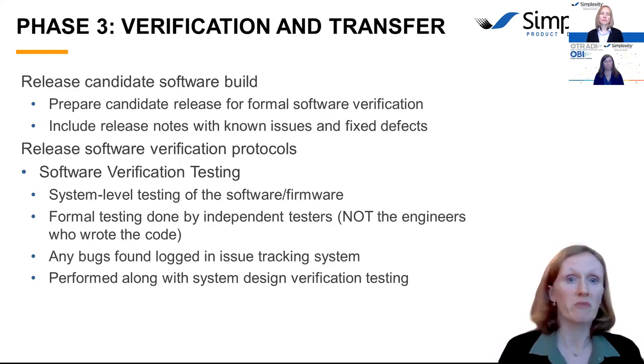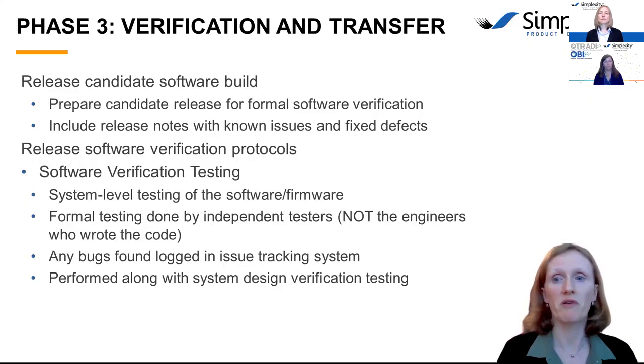Before that formal verification begins, the software team has to prepare a candidate release build. This will include release notes with a list of known issues, a list of what features are included, and any bugs that have been fixed in this version compared to the previous version, if there was one. This software build is a version that will be used for the formal software verification testing. We sometimes casually refer to this as released software or doing the software release, but it's not officially released until it has actually passed that verification testing. That's a big gate.